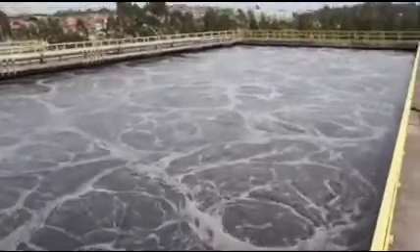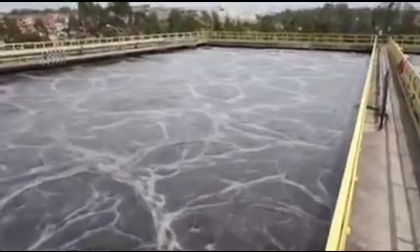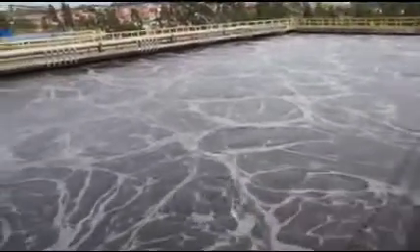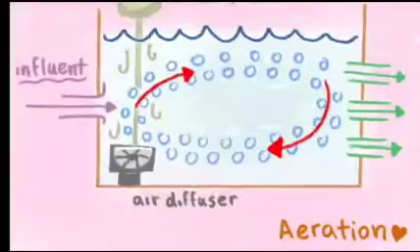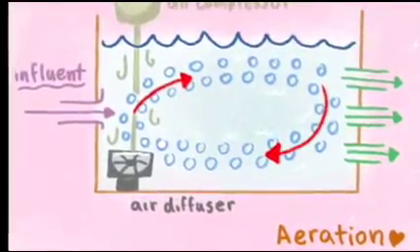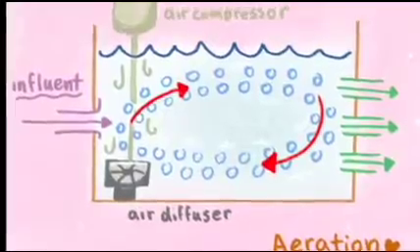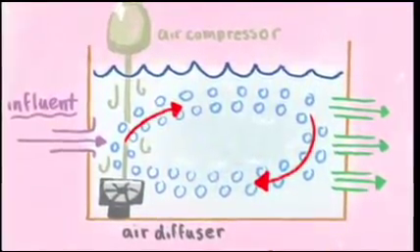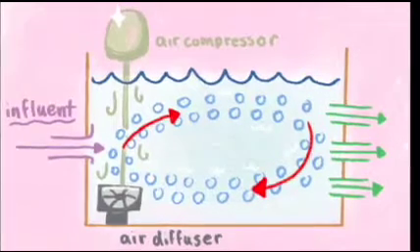We then move on to the secondary treatment process, which focuses on the aeration of the wastewater. Aeration means adding oxygen. Thus, the water is moved to large tanks bubbling with added air. This is similar to pumping air into a fish tank, but on a much larger scale. The air is added so that the bacteria can eat or oxidize the biodegradable carbon and ammonia in the waste.